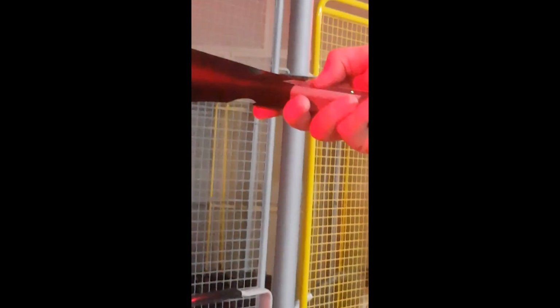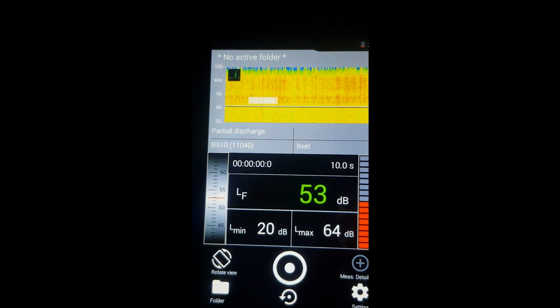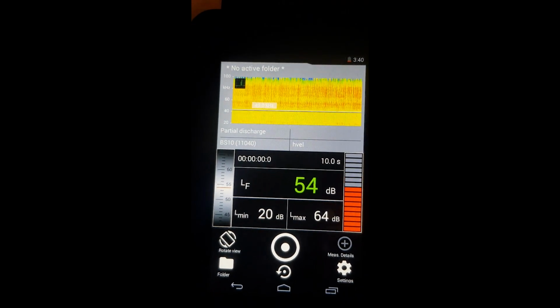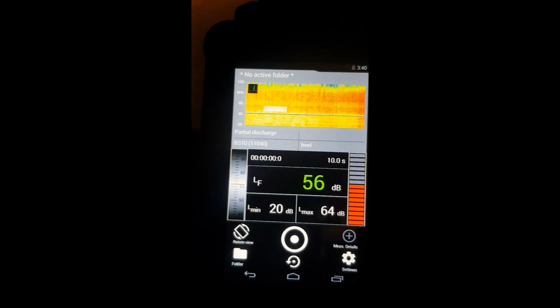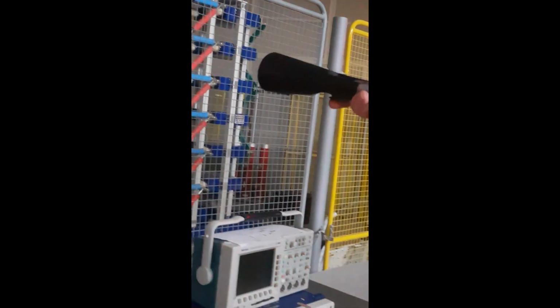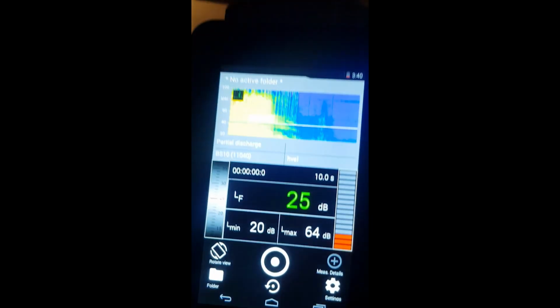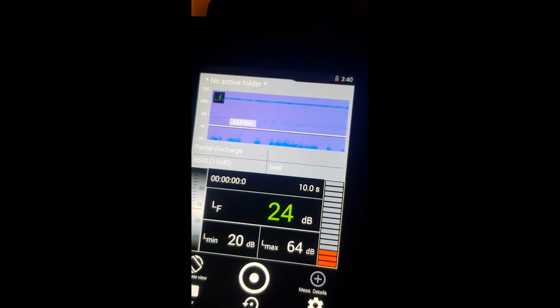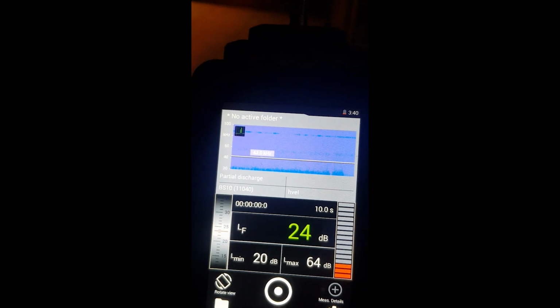Now here we detect dry band arcing using the ultrasonic sensor. So here the sensor has its horn antenna here, connected to the sensor. When you look here clearly, you can see the detection of these ultrasonic sounds, very clear, very intense. Now we will just point the horn antenna away from the source. You can look here now, it went away because this is a very directional sensor. It can only detect when you are pointing towards the source of the arcing. And this is one of the advantages of the ultrasonic sensors.